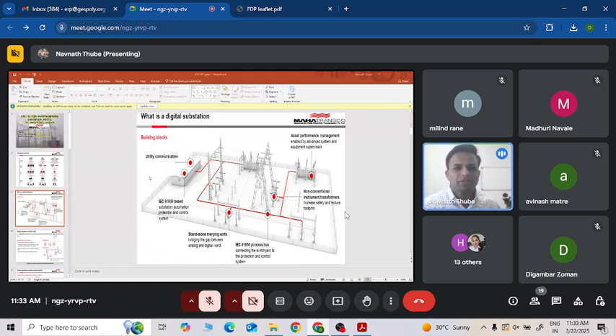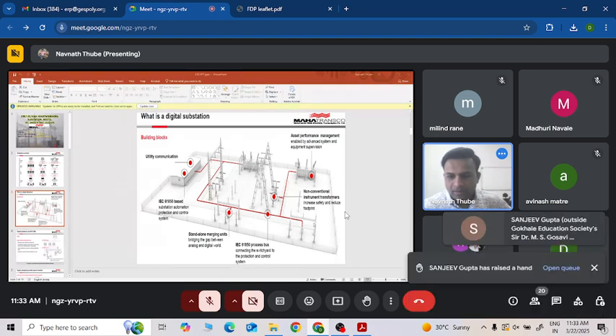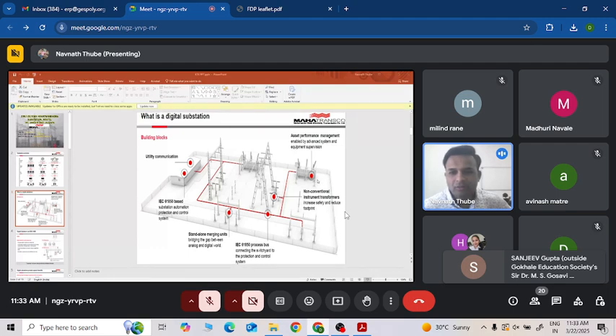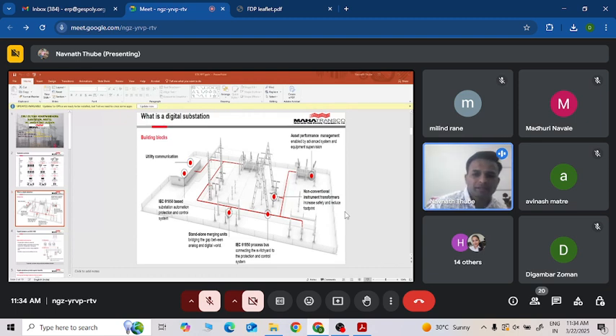Digital substation with process bus. These are all the switchyard equipment. After that, we get the data on this process bus, and through the process bus the same data can be transferred to our control room, that is the utility center, through the digital bus using the IEC 61850 protocol. All signals are digital at station and process level. All information is available on the communication network along with measurements and switchgear status. Monitoring, control and protection commands are highly available on a fiber optic basis. Information is acquired once and distributed to all.